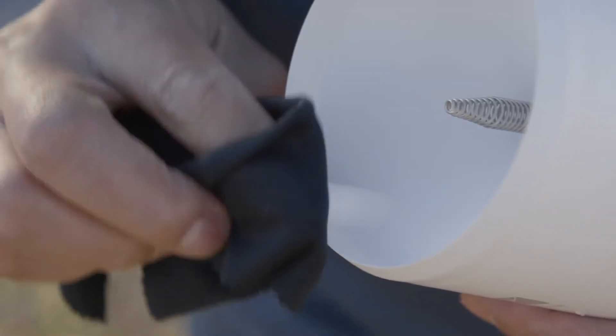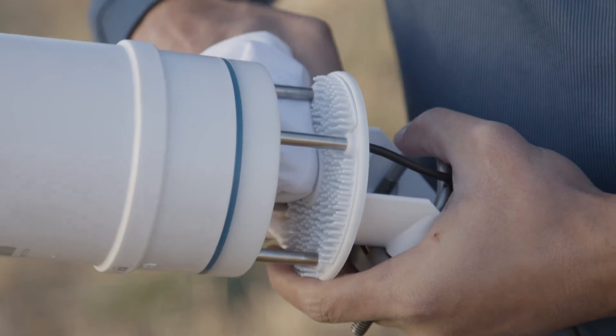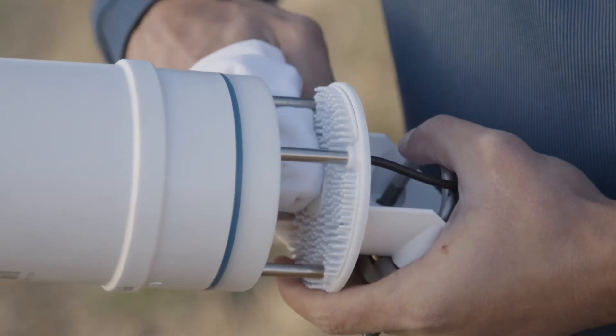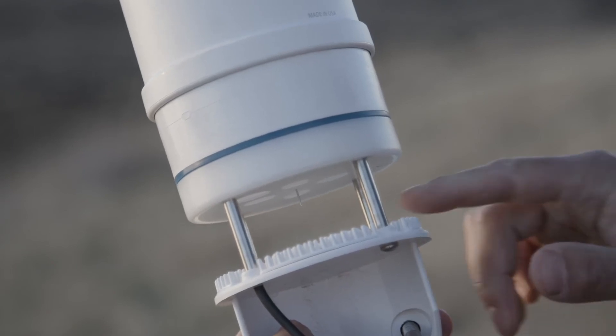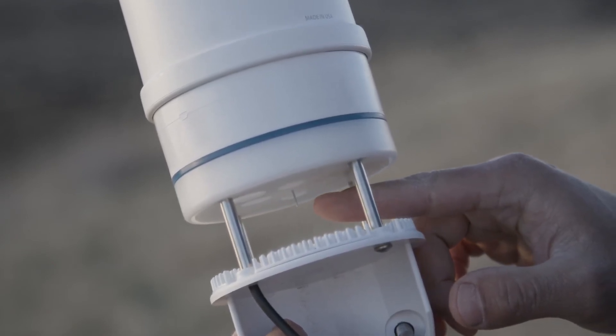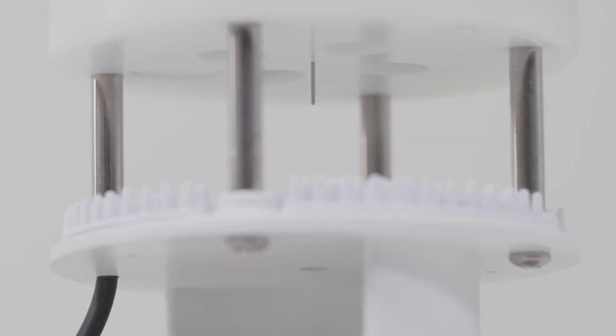Use a dry part of the lens cloth to dry off the pyranometer. To clean the Atmos 41 sonic anemometer, use a damp or dry cloth to wipe off dust and debris on top of the acoustic plate. Be careful not to touch or bend the metal temperature sensor during the cleaning process. It's very delicate and can be damaged, but check it closely for corrosion.